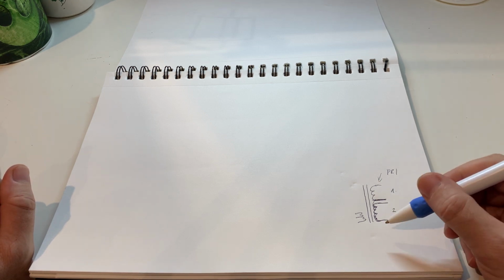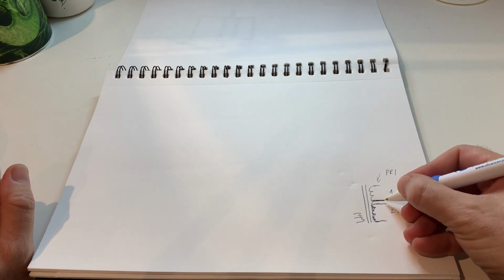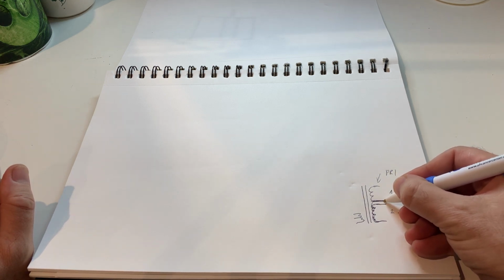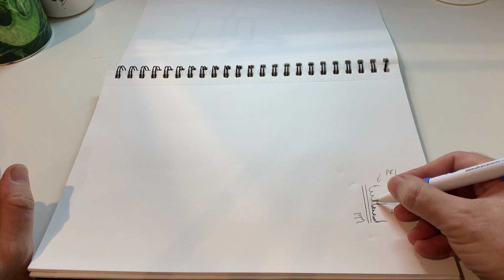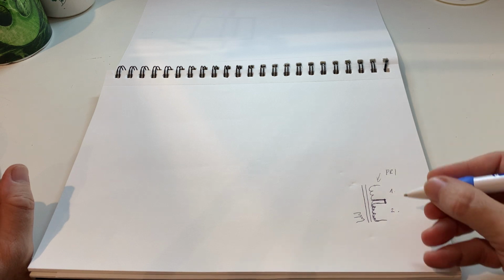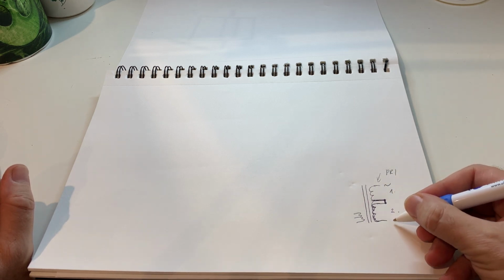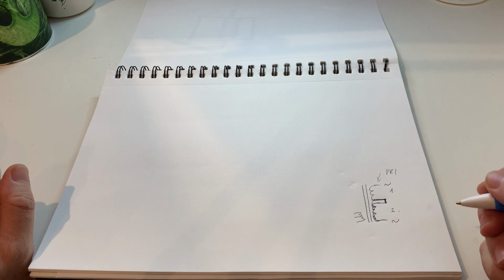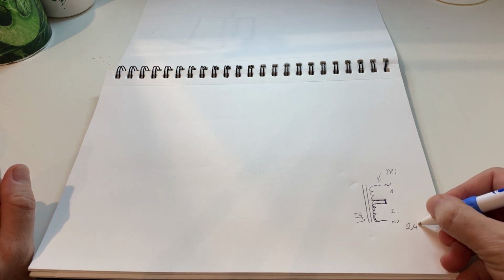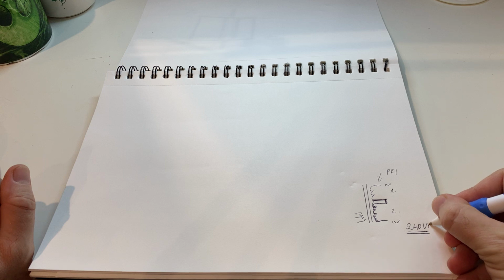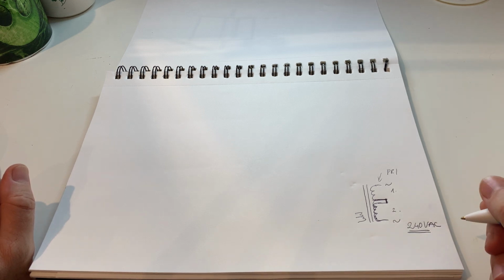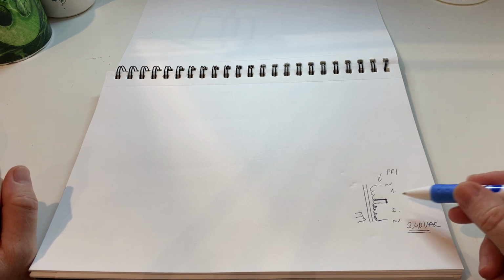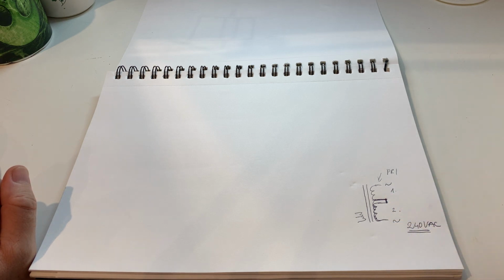If we connect them in series, we connect the lower terminal of the first coil to the higher terminal of the second, and this connects to the line voltage. Then we have 240 volts AC operation. So if in your country you have 240 volts in your wall, you connect it this way.